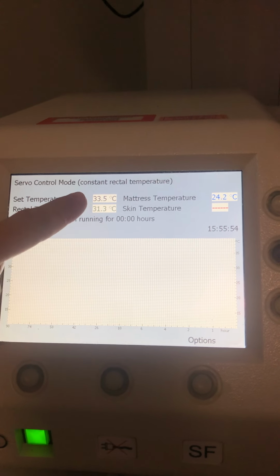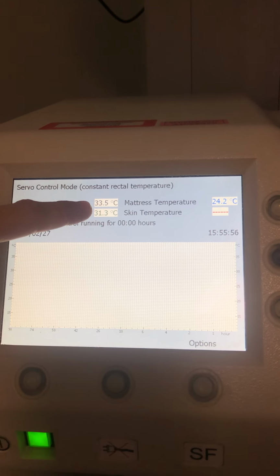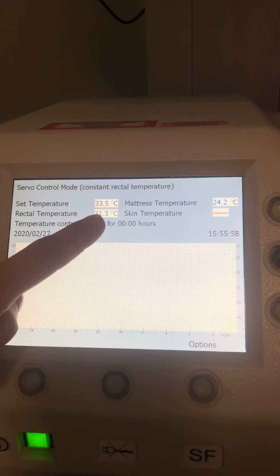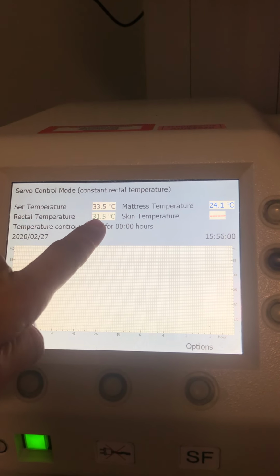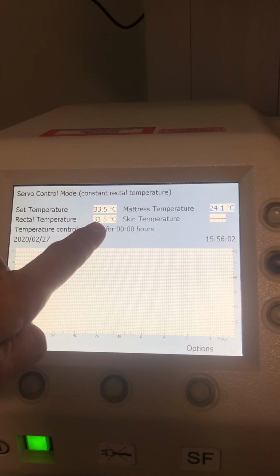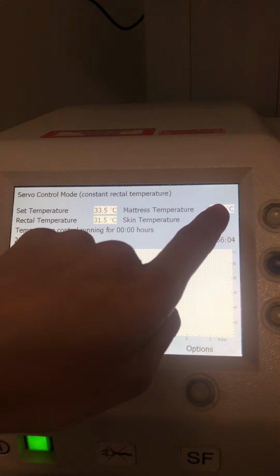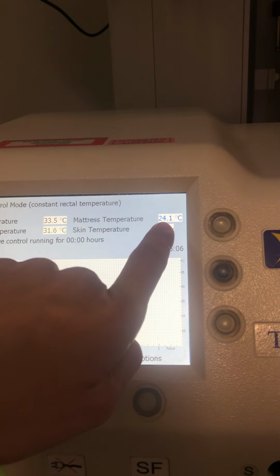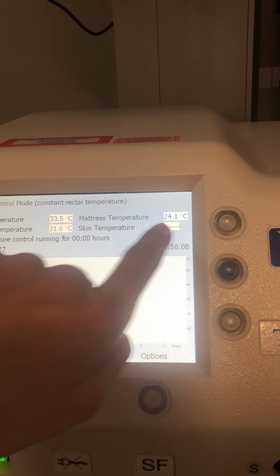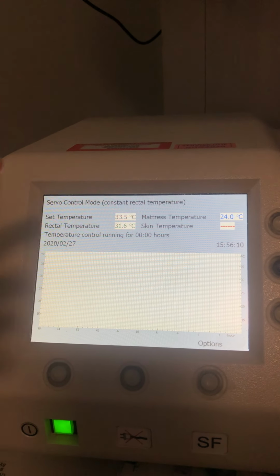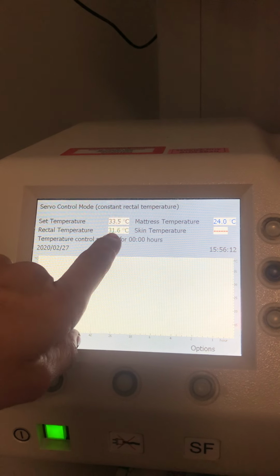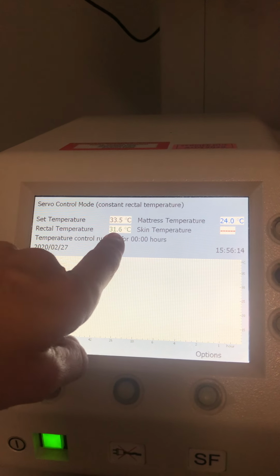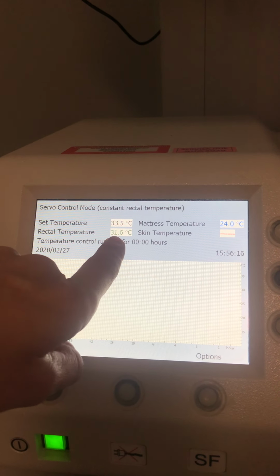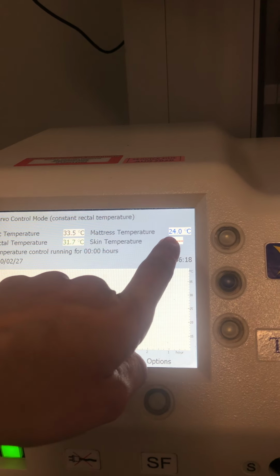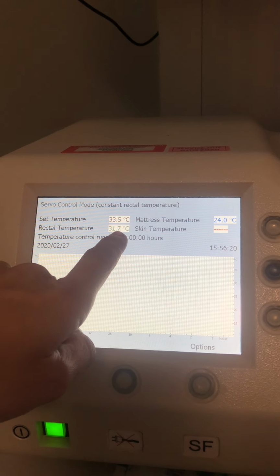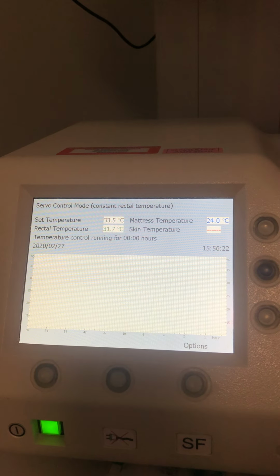You want to be looking at what you set the temperature at, so we want it to be 33.5, and what the rectal temperature is at. At the minute, the baby is a little bit too cold at 31.5. So the mattress is going to start to warm up to get that baby warm. What you will see is the opposite: this should be around 36, 35 if you started knocking the heaters and everything off. So this will actually start to drop to bring that temperature to what it is happy with.